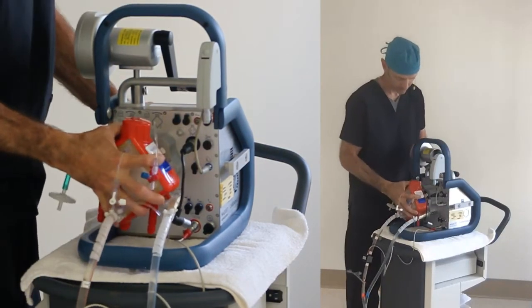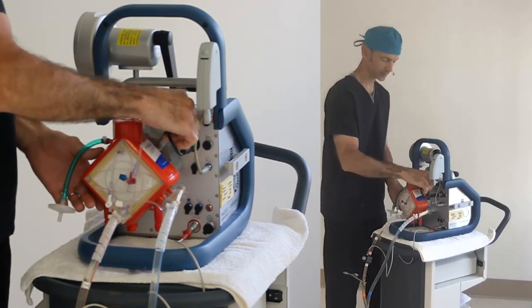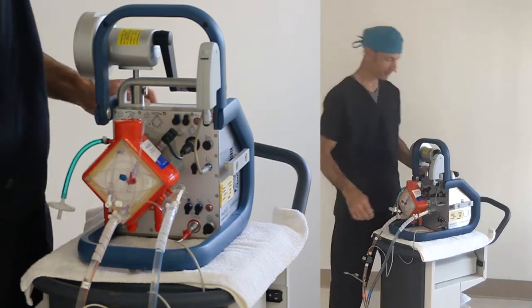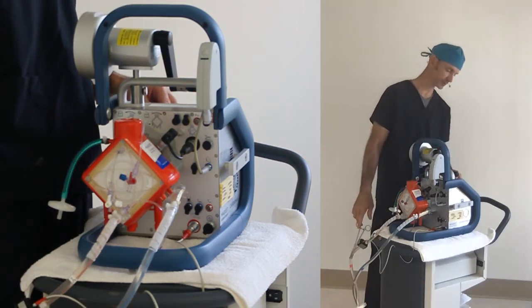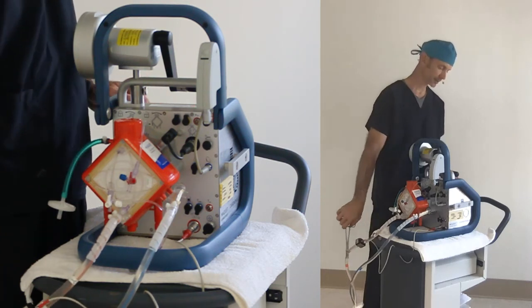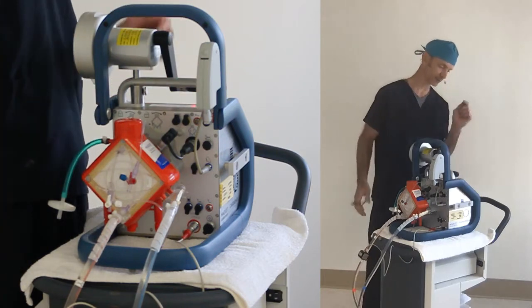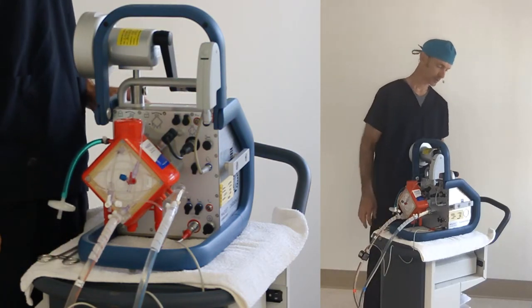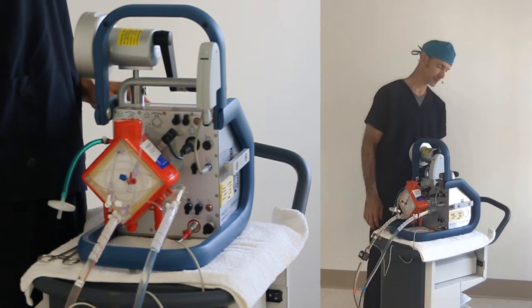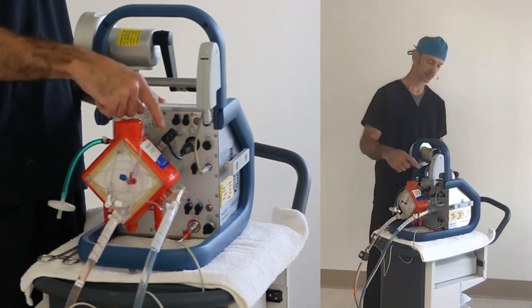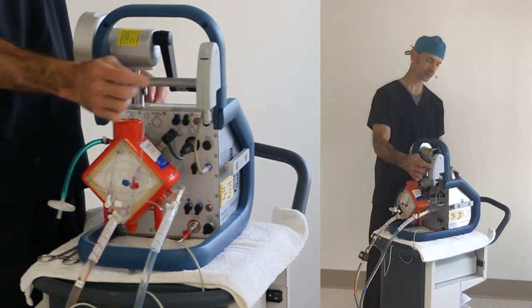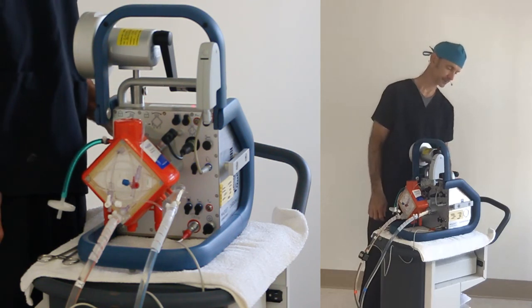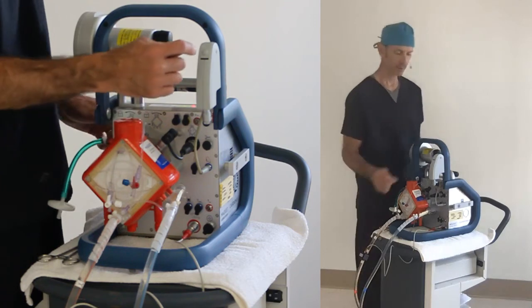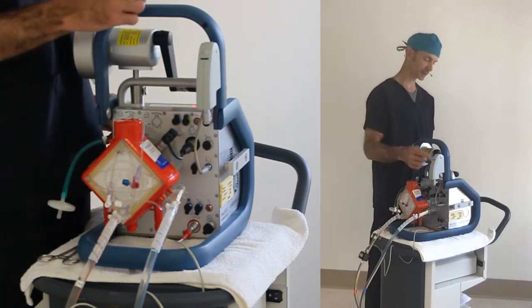Put it in, lock it in place, hook the data cable up since I'm right here, and generate some RPMs. Get my 1,000 RPMs, take the clamp off the line, we have flow. Come up to full flow. I have pressures. Because I hooked in the data cable. What I don't have yet is the SVO2. But it's not alarming because it's on the docking station and is happy up there.